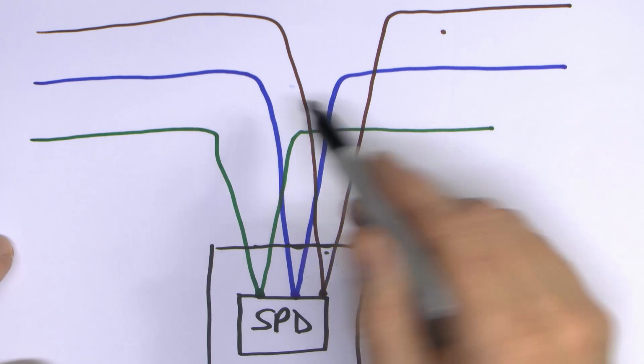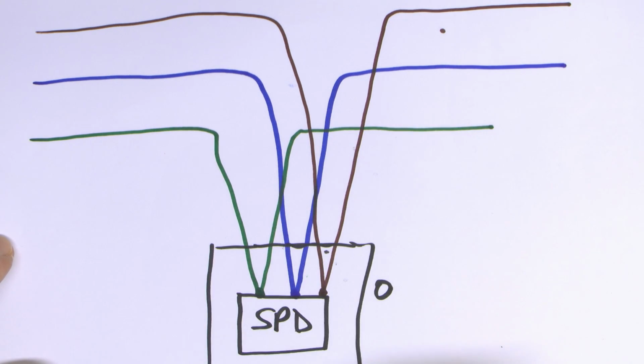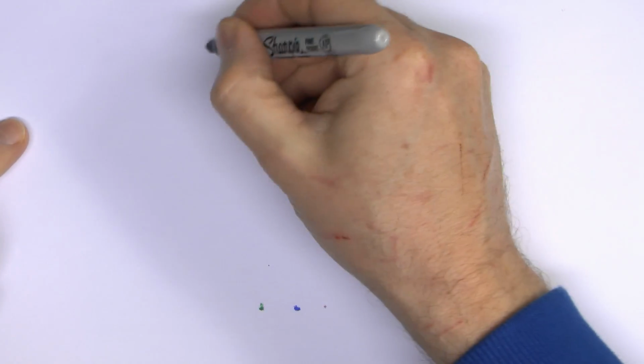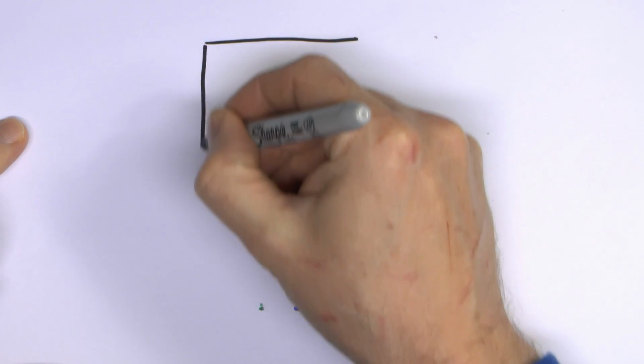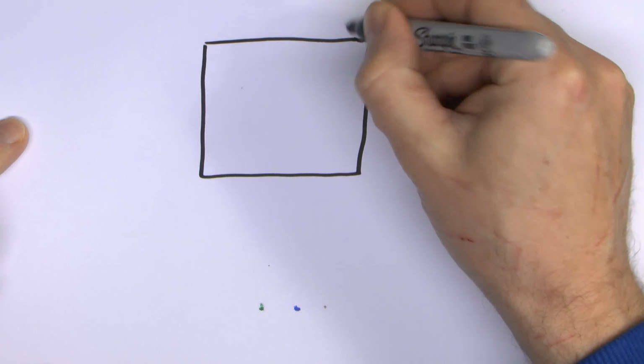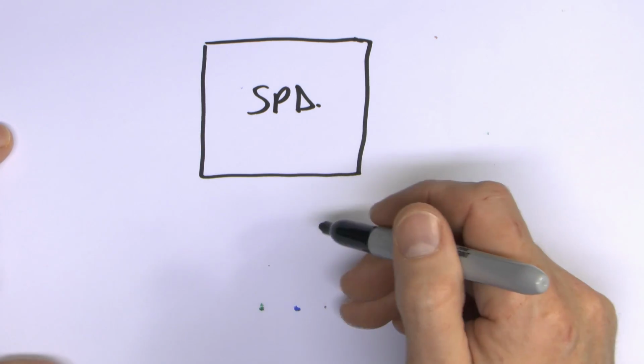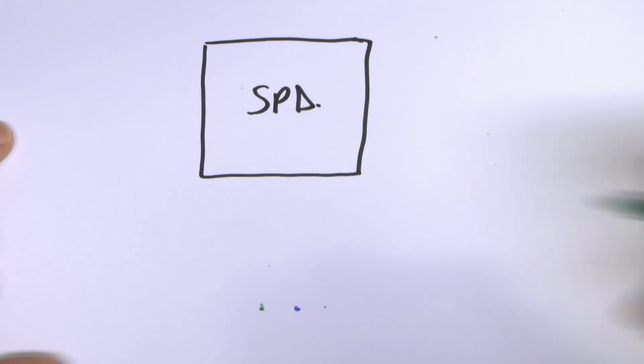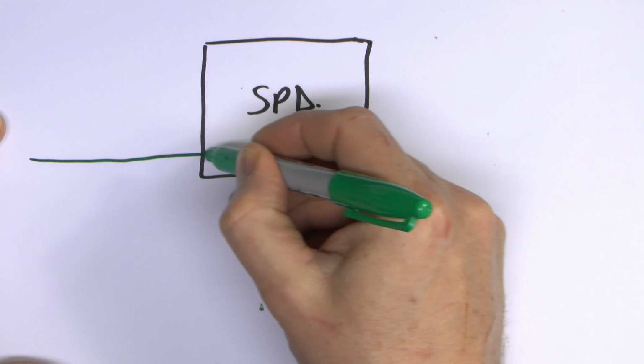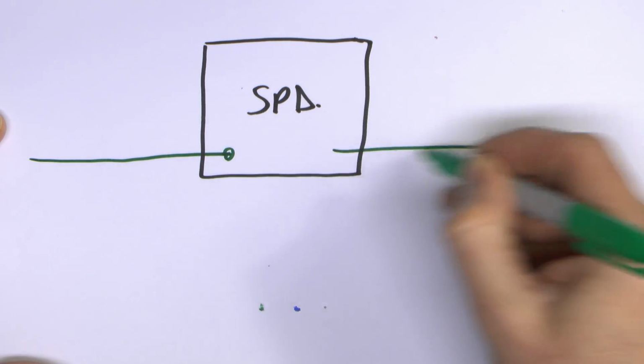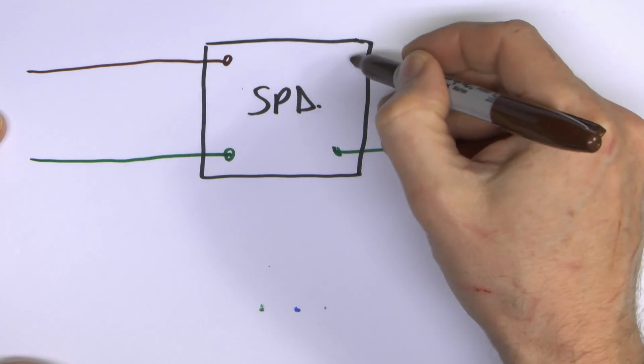So if you must have the wires coming across, going in and coming out on the same side, that is a far better way of doing it, and it sort of minimises the distance there pretty much down to nothing. And another way you can do it, which is similar to that Wylex item we saw previously, is you have your surge protector device here, and as with the Wylex one it's got two sets of terminals either side, so your wires can come in to the device and then just go out the other side. And of course the same with the other conductors as well.